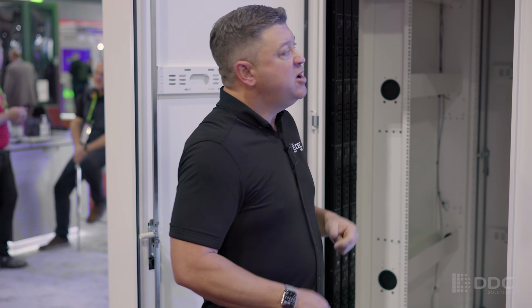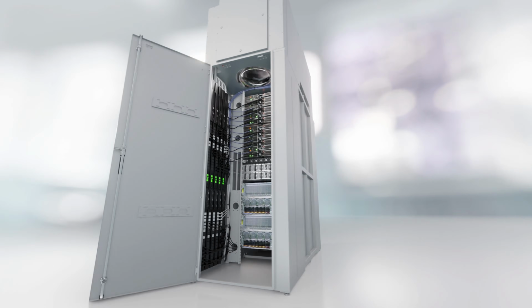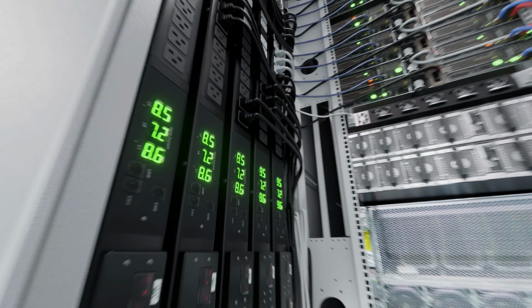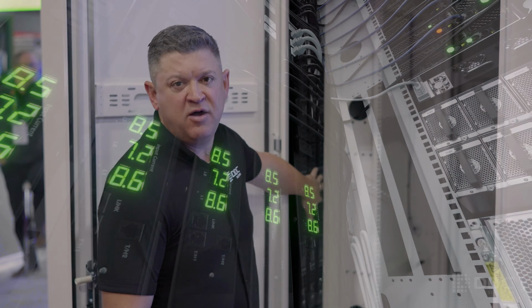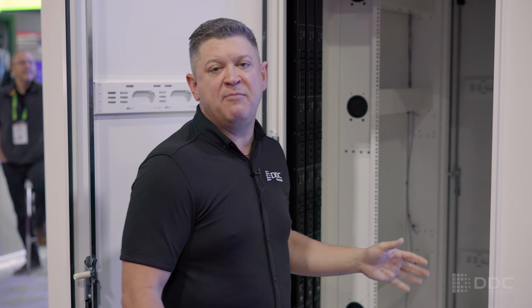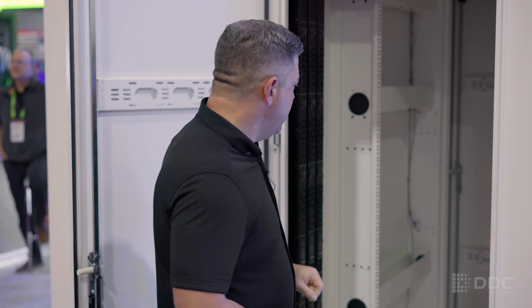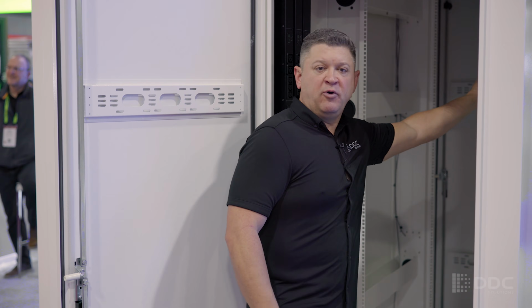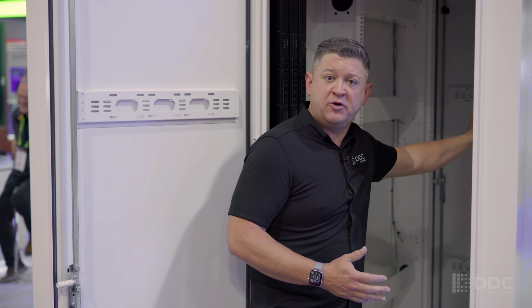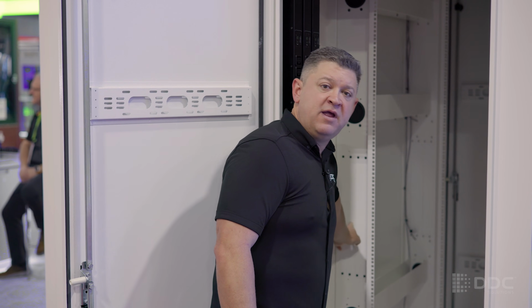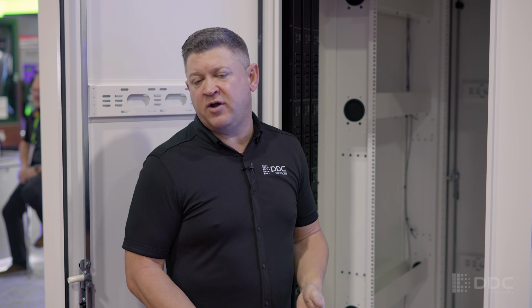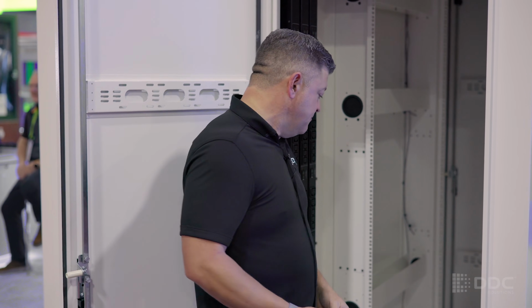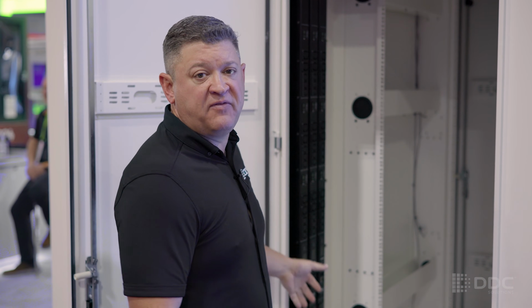Beyond that, we've got mounting brackets for a tremendous amount of power and power strips in the back of the cabinet—you'll see a number of these mounted behind me. We can mount up to 5 on each side, allowing us to reach the extremely high densities this platform can cool. You'll also see adjustable rails supporting cable management and longer server depths, zero-U server mounting for additional switches outside a traditional cabinet build, and sensors throughout the back to manage rear-side temperature, important for ensuring servers don't overheat with higher heat loads.